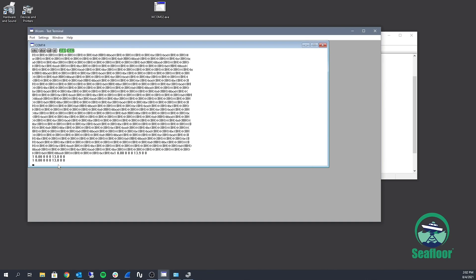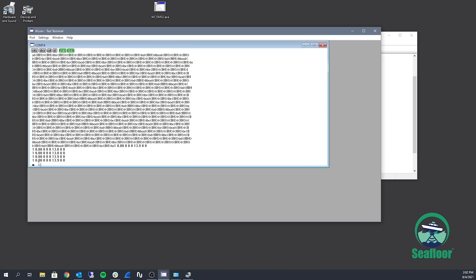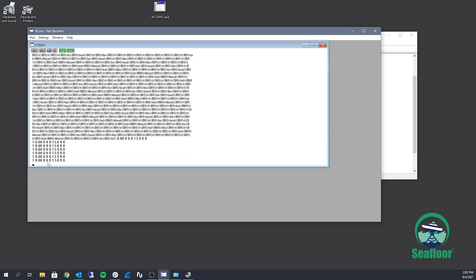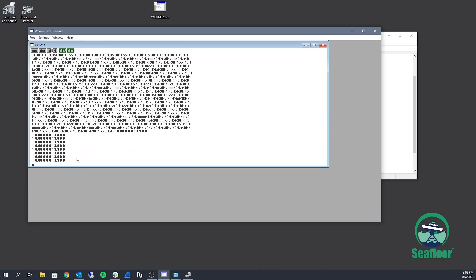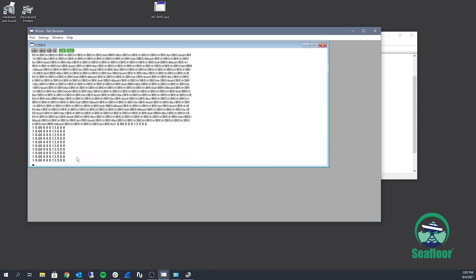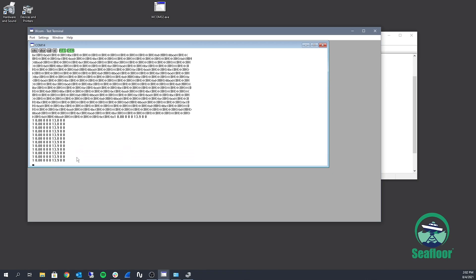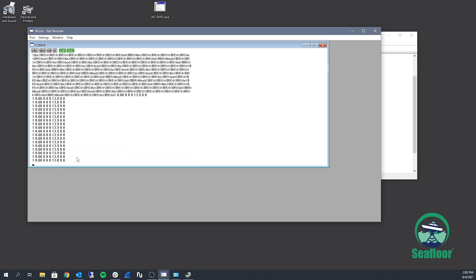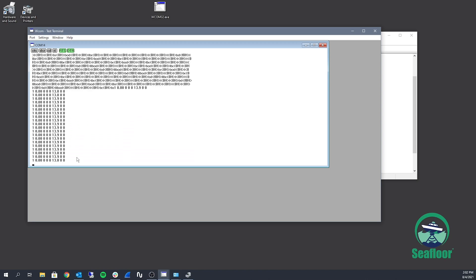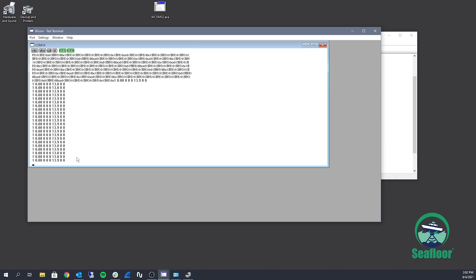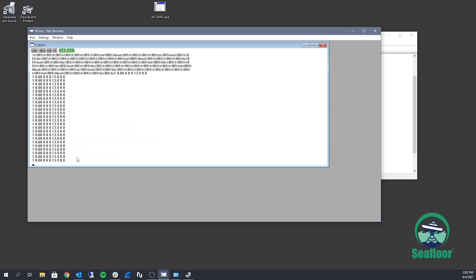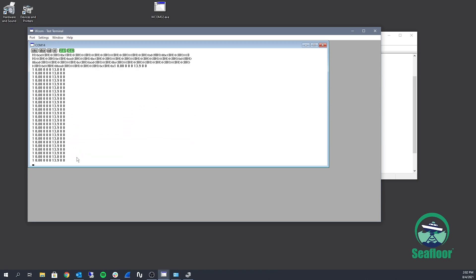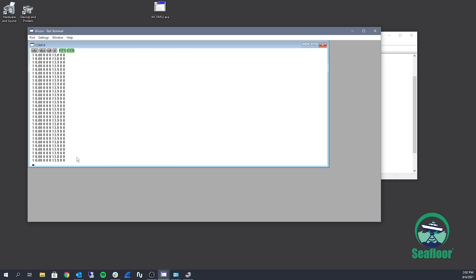It's useful to open up and see your raw data string in WCOM in case you might not be getting values from your transducer or your batteries too low to actually produce a ping. So this is one of the troubleshooting steps that I usually do first to make sure the unit is working properly.